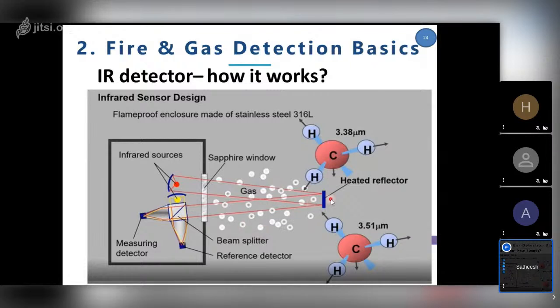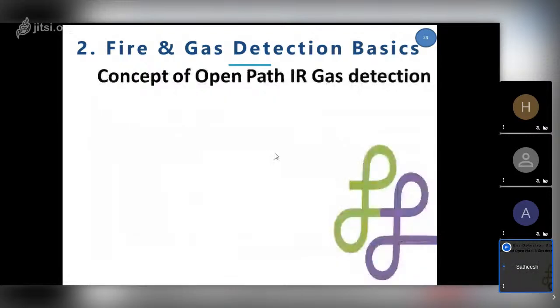So if there is no gas, this detector and this detector both will be seeing the same reading because there is no absorption due to absence of gas. When there is a gas, it is expected that this red beam has some absorption due to the gas molecules. So the measurement detector will see a drop in reading, whereas the reference detector will be at full signal because it is not exposed to the gas. So we compare it, and then finally we decide there is a gas leak, and we give a reading to alert people that there is a flammable gas leak, for example, methane or propane or butane.